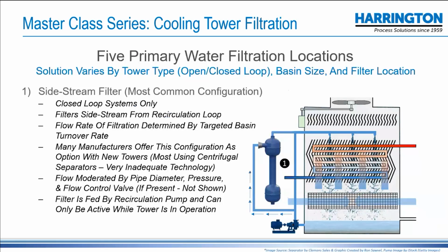So there are 5 primary places where you would filter for cooling tower operation. Now, 4 of them are relative to the cooling tower. The other is relative to the plant and the heat exchanger. By far, this is the most common configuration. And also, by far, the most commonly used method isn't a filter, it's a separator. It works on centrifugal separation to spin solids within that unit, which theoretically is going to cause them to slough off to the side and drop down into a collection bell.